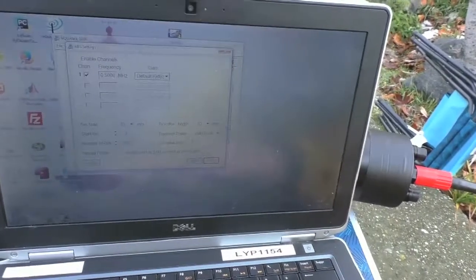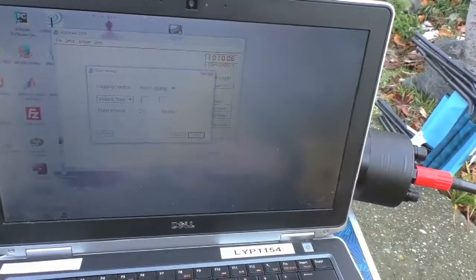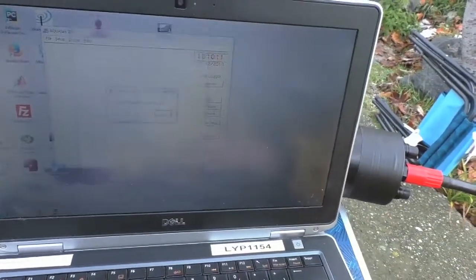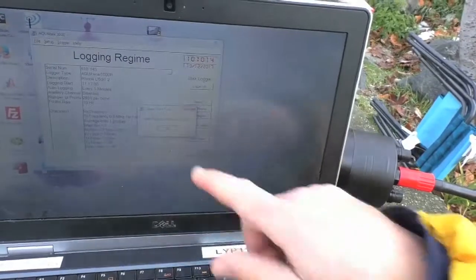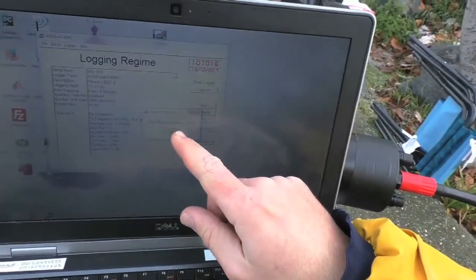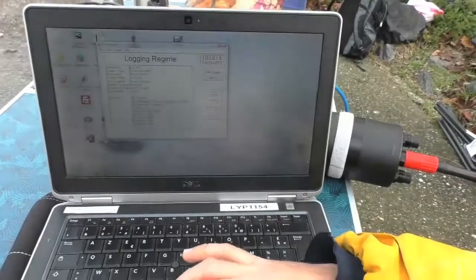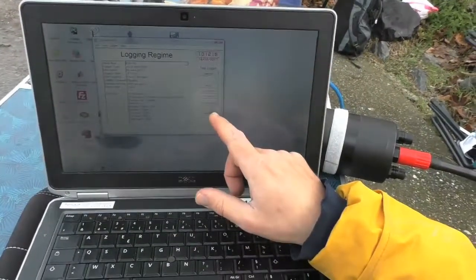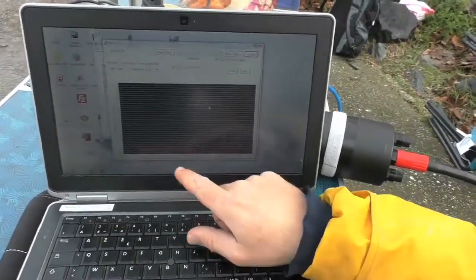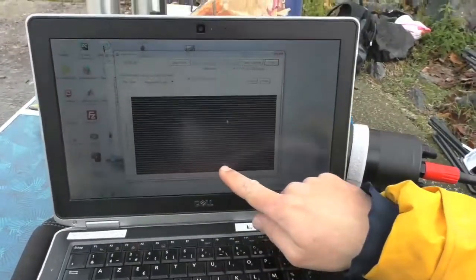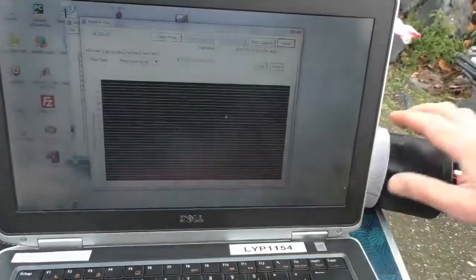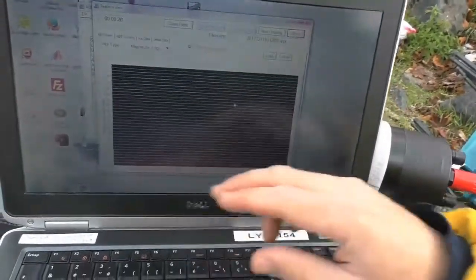The logger time, next, just until next. Okay. The setup is done and we start at 11 past 10. When the instrument starts to record, we click on real-time display and check whether we can see some signal. This check is important prior to the deployment to be sure that everything works well. Most usual issues include low battery and communication with the instruments, most often because of broken cable or laptop driver issues.